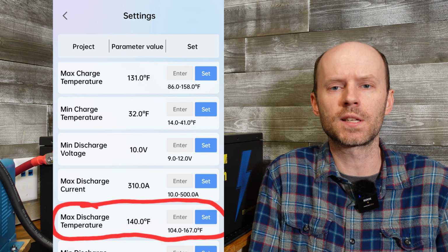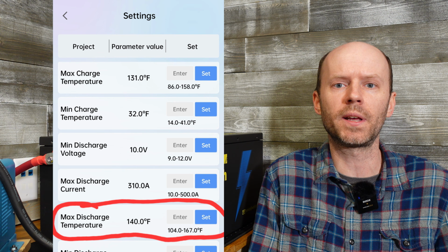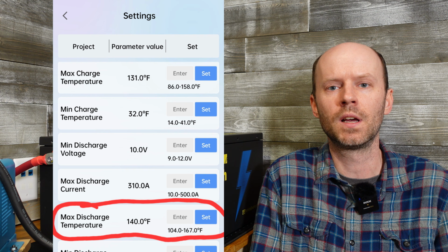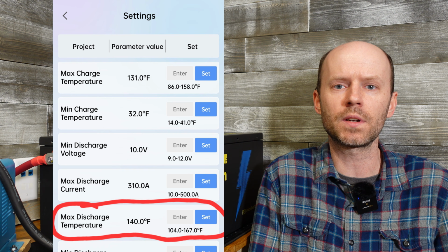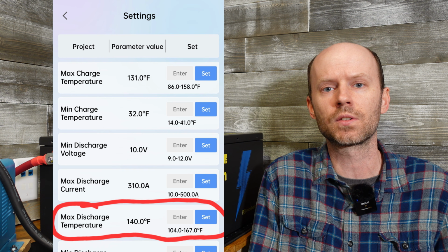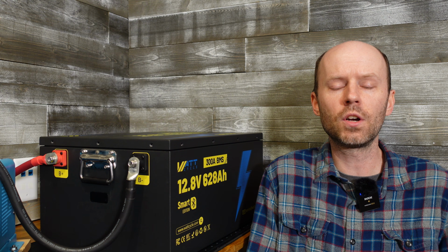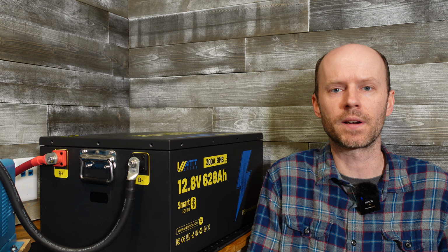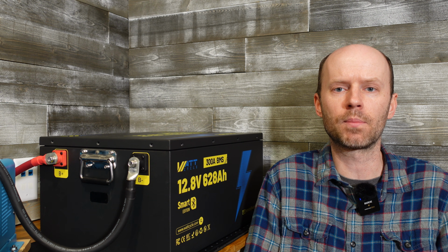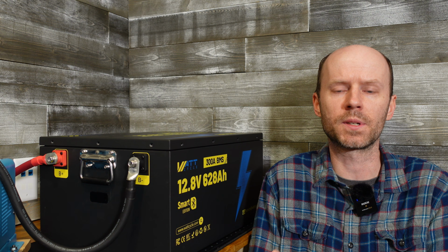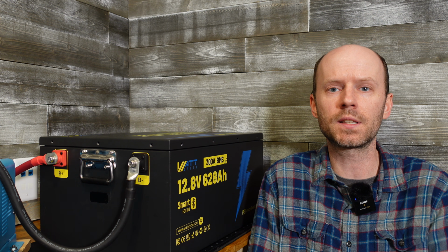So I reached out to WattCycle for clarification on this, and they explained that the 140-degree temperature protection is specifically for the cells themselves. That is sensors T1 through T4. The over temperature protection for the MOSFETs is 221 degrees Fahrenheit. So everything we were seeing was perfectly normal and still within the expected operating specifications. But I still want to make sure the over temperature protection on this battery works. So let's get out the heat gun.